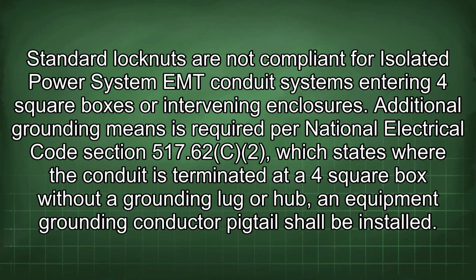Standard locknuts are not compliant for isolated power system EMT conduit systems entering 4 square boxes or intervening enclosures. Additional grounding means is required per National Electrical Code Section 517.62C2, which states where the conduit is terminated at a 4 square box without a grounding lug or hub, an equipment grounding conductor pigtail shall be installed.